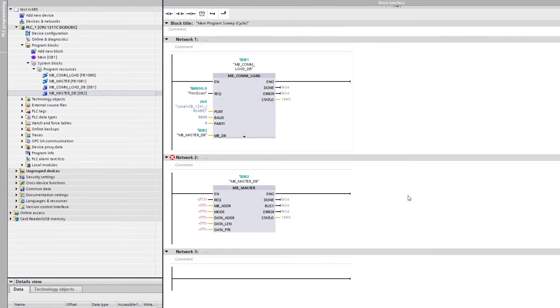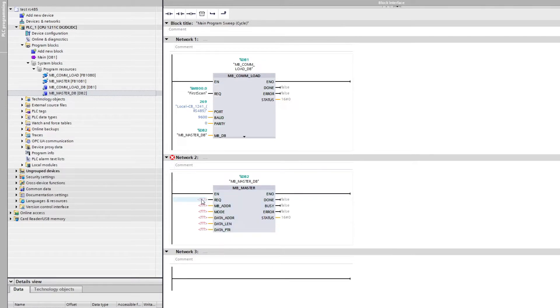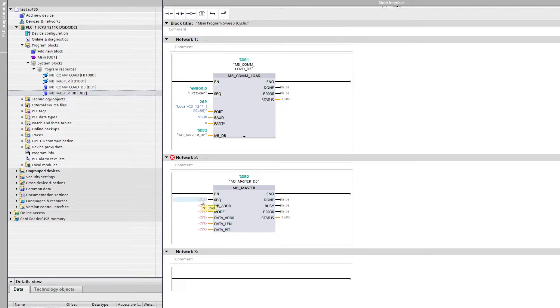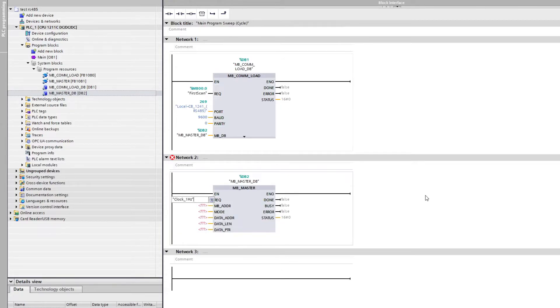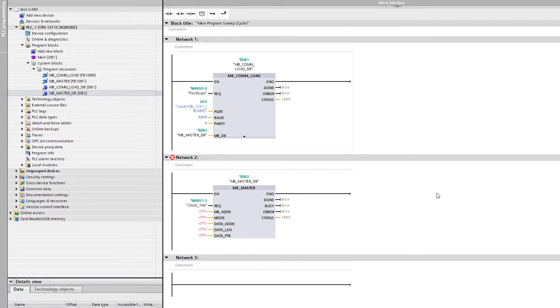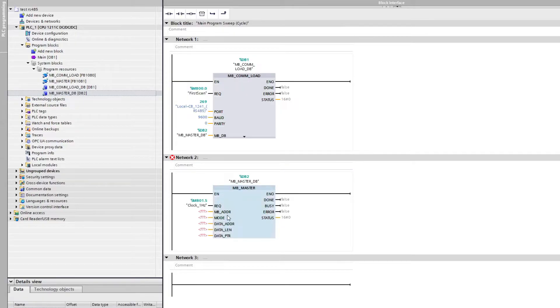On the Modbus master block's request input, we can add the clock 1Hz. This will make the block request every second to read or write from the slave. For the other inputs we can click on the block and press F1 on the keyboard to open up a help menu.